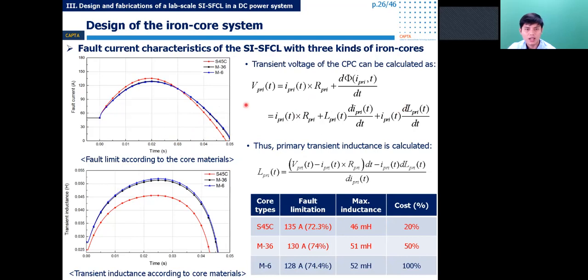In theory, the SFCL limits the fault based on the transient inductance of the primary coil. So we can calculate this value based on the transient voltage and transient current. As a result, you can see here, the fault limit of the SFCL with different core types was not significantly different. The limitation rate was higher than 70% in all cases. But considering the material cost, we selected the S45C core and the M36 core to manufacture, test, and compare in the experiment.